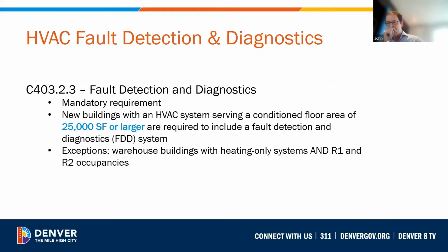So for the first requirement, HVAC fault detection and diagnostics, it's a new mandatory requirement for buildings with an HVAC system serving a conditioned floor area of 25,000 square feet or larger. There are systems that are exempt, including those that serve warehouse buildings with heating only systems and those serving R1 or R2 occupancies.